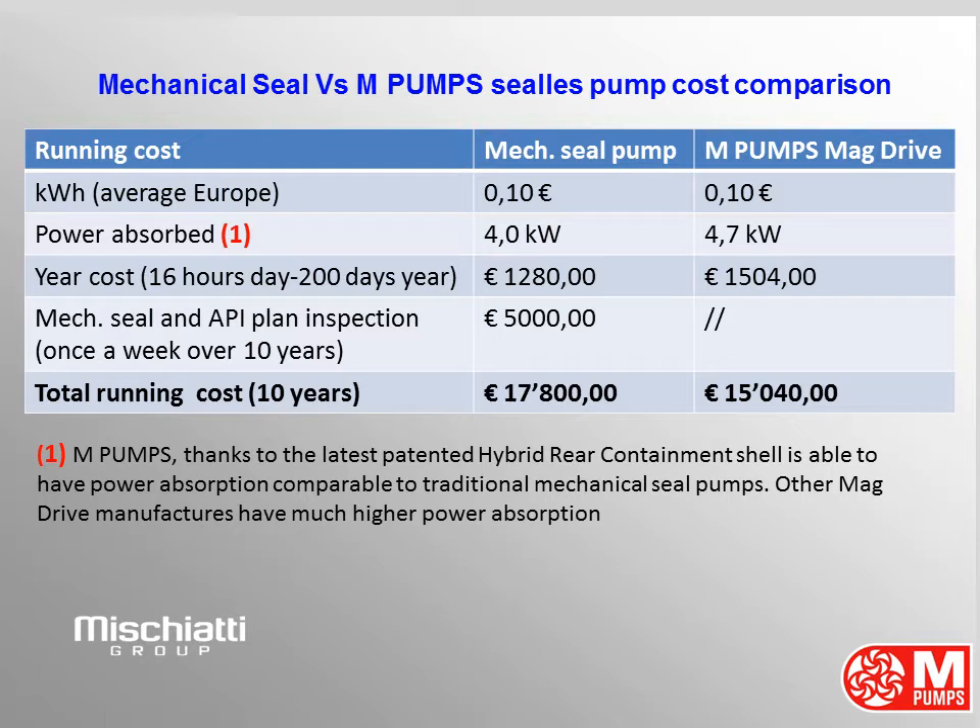If the pump works 16 hours per day and 200 days per year, your energy cost is 1,280 euros for the mechanical seal pump and 1,504 euros for the magnetic drive pump. Mechanical seal pumps also need a mechanical seal and API plan inspection once per week — over 10 years this means 5,000 euros in cost. Total running cost over 10 years is 17,800 euros for the mechanical seal pump and 15,040 euros for the M-Pumps magnetic drive pump. With M-Pumps you save money again.